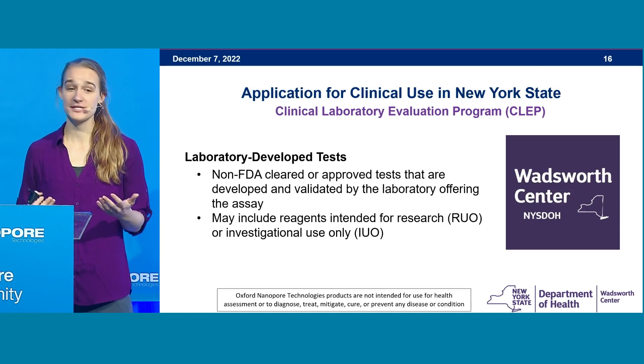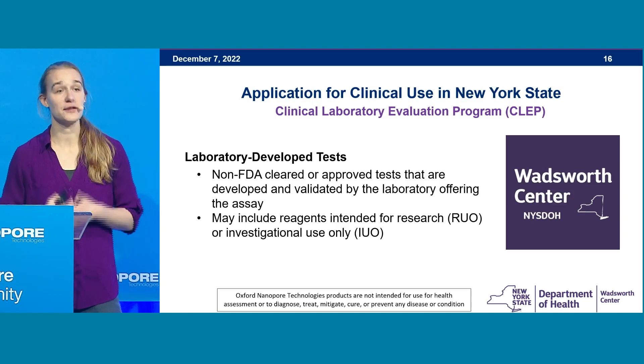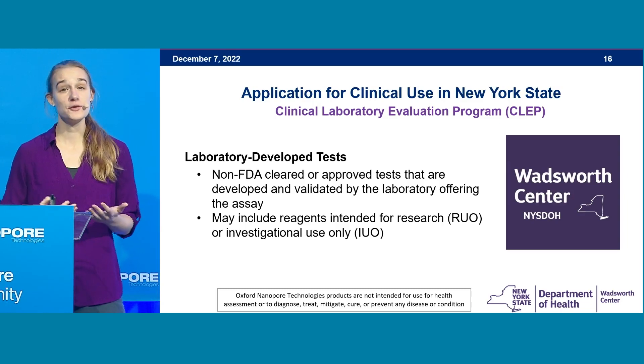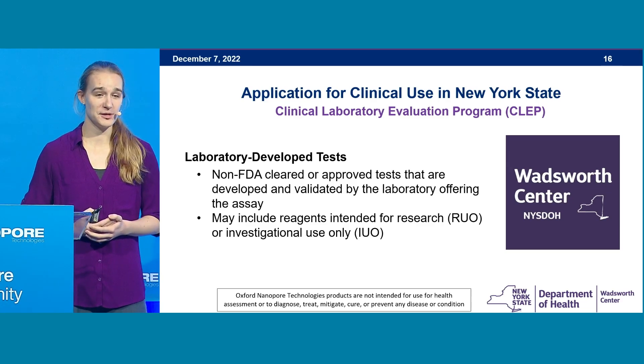It's important to note that nanopore technologies are not approved for clinical use. But in New York State, we have a Clinical Laboratory Evaluation Program that reviews new laboratory-developed tests, including assays with reagents intended for investigational or research use only. As part of those evaluations, we perform testing that looks at sensitivity, specificity, reproducibility, and accuracy of proposed tests before they are implemented in the laboratory.